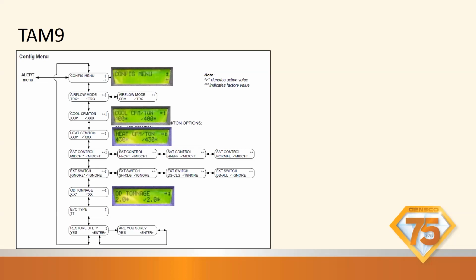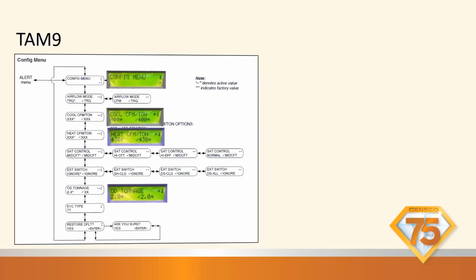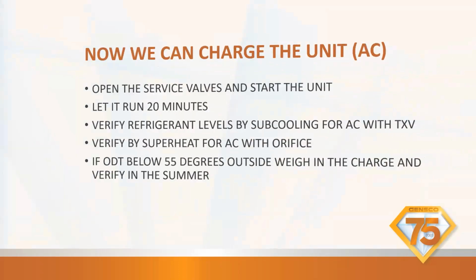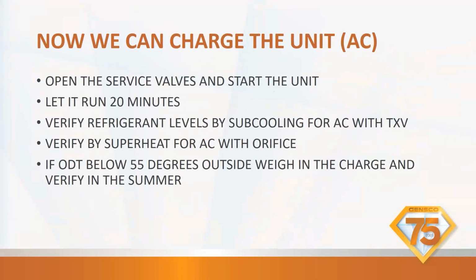Then you go down, you go to the outdoor tonnage, tell it what ton the outdoor unit is. While you're in there, you should tell it what type of electric heat it is and set up your electric heat strip size so you don't have to go back in there twice. Now that we've done all this, now we can charge the unit. Now we can get down to the good part, okay?